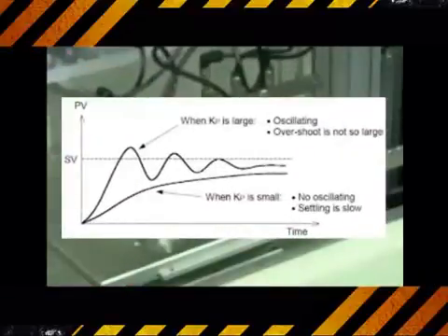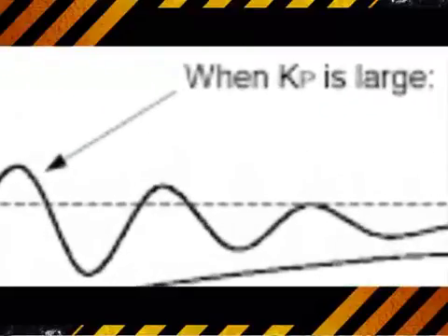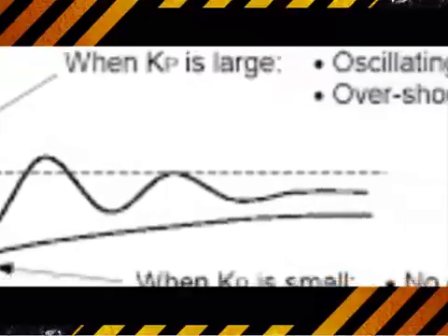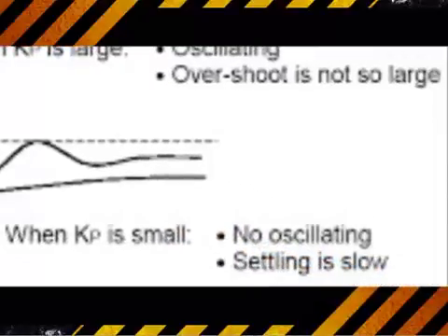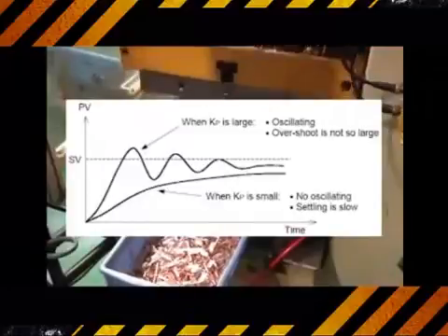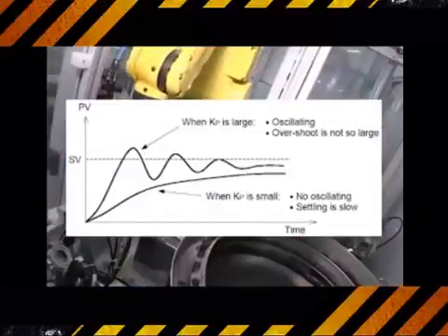That's why too much P gain in a control loop sends it unstable. The actuator doesn't back off quick enough, you overshoot, and then make the exact same mistake going the other way, and on and on. So the trick is to find a P gain that is high enough to give you the speed of response that you need, but not so high that you go unstable. So why don't all control loops use a P-only controller that is beautifully tuned not to overshoot the set point and leave it at that?